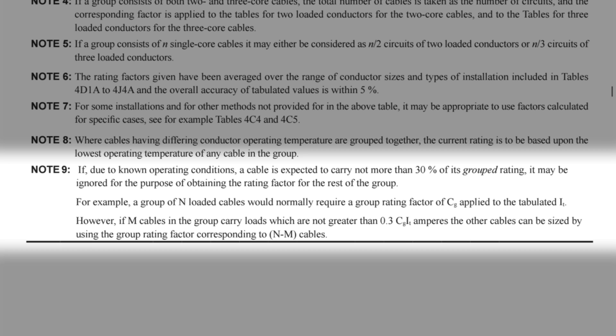So in other words, if the cross-sectional area of the cable is bigger than it needs to be — which sometimes happens to make the circuit have a compliant volt drop or earth fault loop impedance value — then we may not need to include it in our calculation for grouping. This is because the circuit is not drawing enough to make the cable hot enough to cause a problem. But there are two points to be careful about.